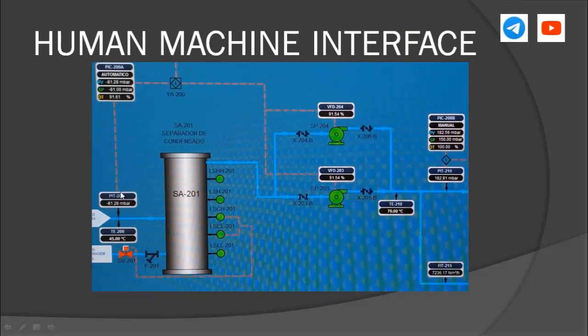So we have a measurement of the pressure, we have a measurement of the inlet temperature also, and the automatic drain valve, and we have the switches here, and we have the two blowers with VFD, and the set point for controlling the pressure in the suction of the machine is minus 81 millibar. And in the discharge of the blowers we have the temperature measurement and also the pressure. And we have also the indication of the flow measurement here.